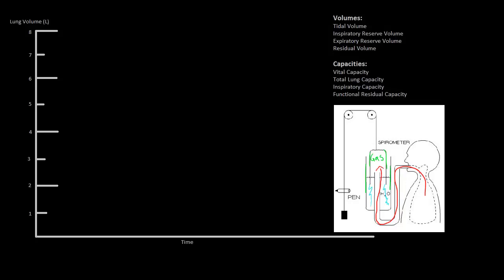When a patient exhales, gas will travel the other direction — out of the lungs, out of the tube, and into the gas enclosure. When a patient inhales, the gas that leaves the enclosure will drop the top bowl, and through a pulley system cause the pen to rise on the paper, giving us an uptick on the graph. The opposite is true when a patient exhales: gas enters the chamber, the bowl rises, and through the pulley system the pen drops on the paper, giving us a downtick.